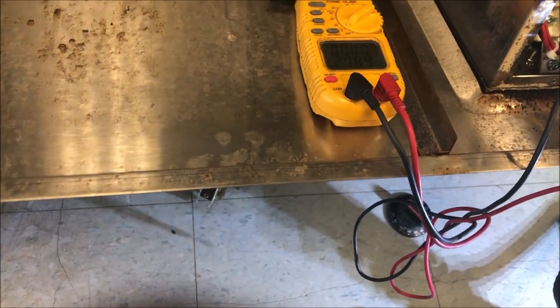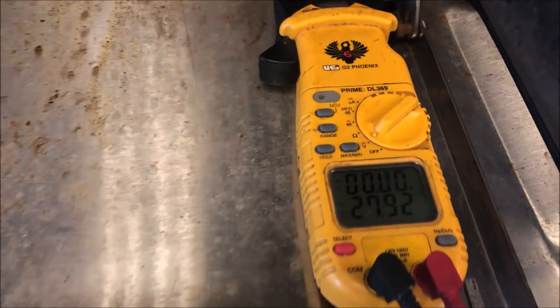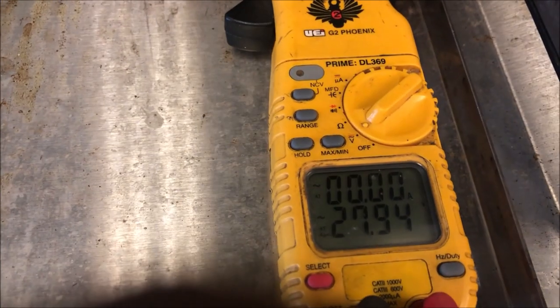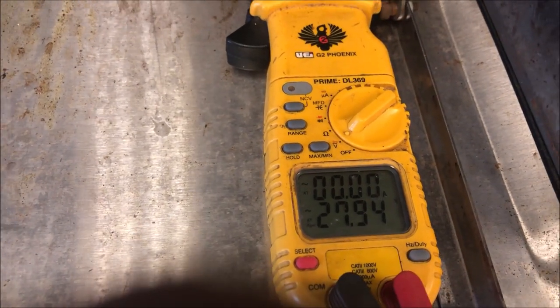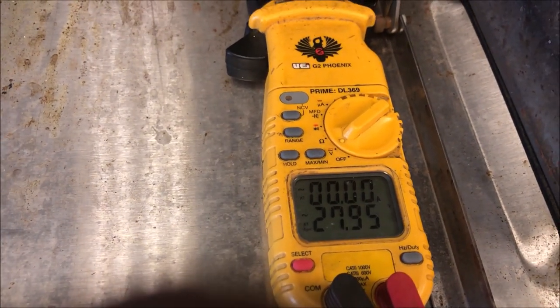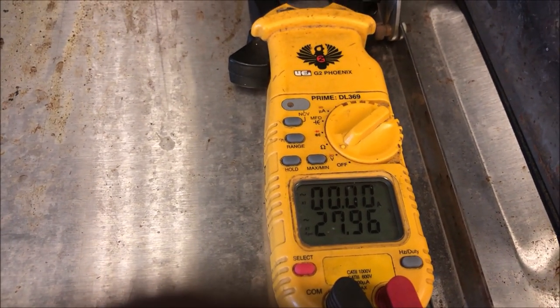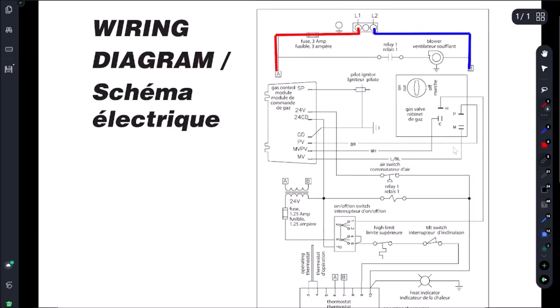Alright so I'm going to test across the limit and we're getting 28 volts - that means it is open. I'm getting 28 volts across this high limit. So what does that mean? It's open.